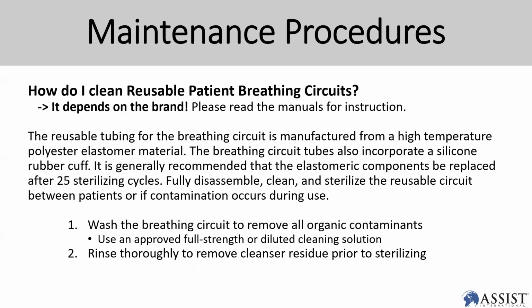So when you come to the maintenance procedure, this is basically about how to clean a reusable patient circuit. It's very important, so make sure it is clean. Some can be used up to 25 cycles, then you need to replace them. How long they last depends on the type of breathing circuit that you get. So you need to wash the breathing circuit, remove all that, then sterilize all this. So this is the maintenance procedure for the breathing circuit.